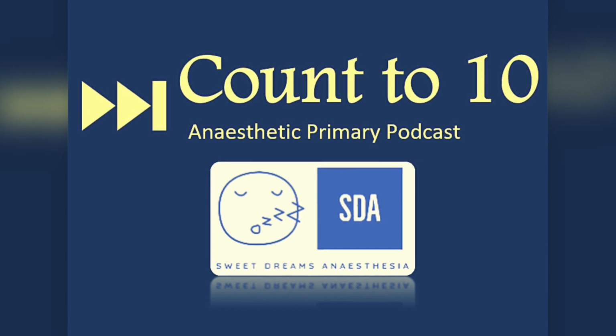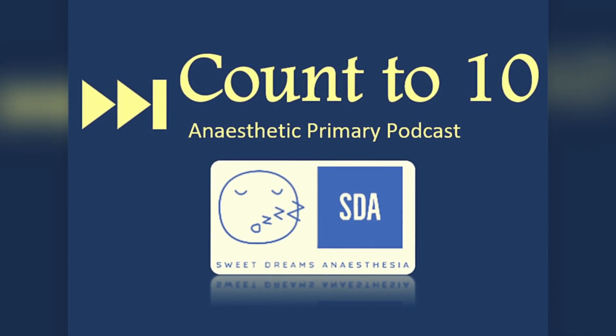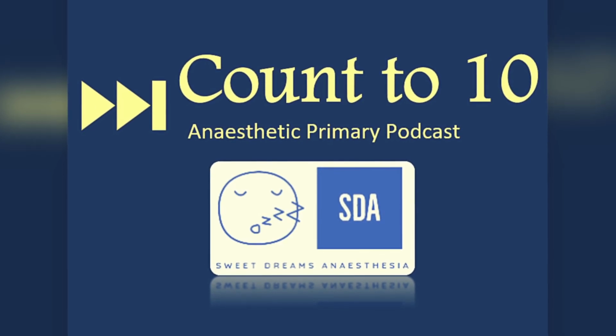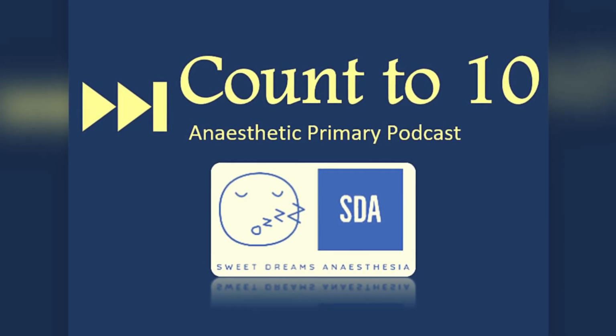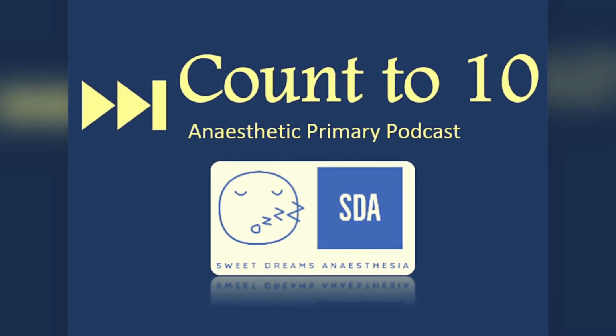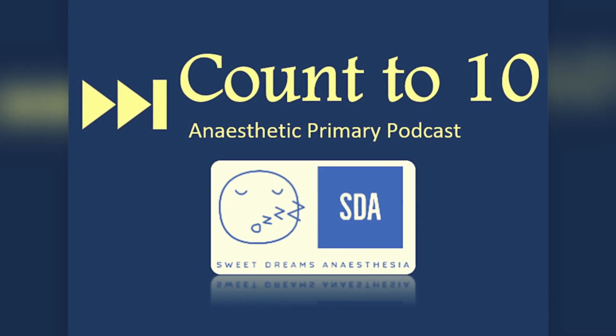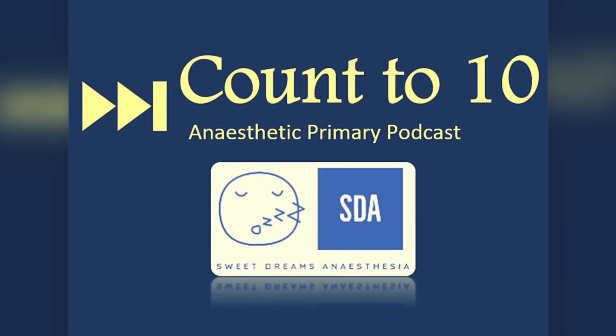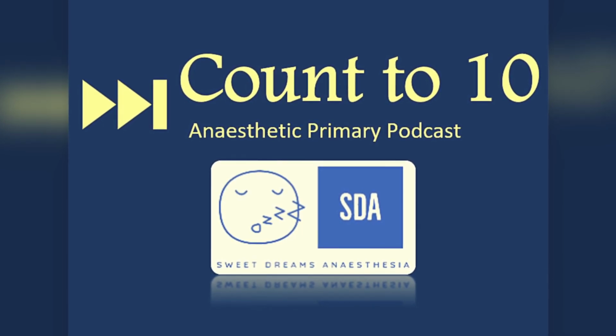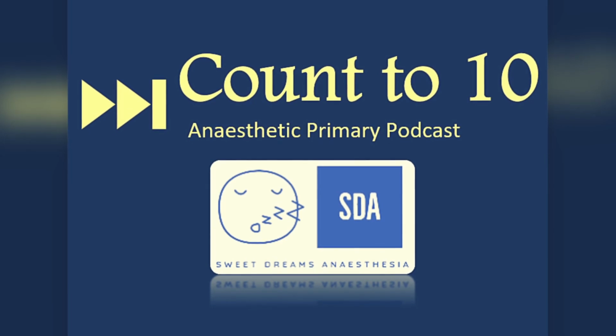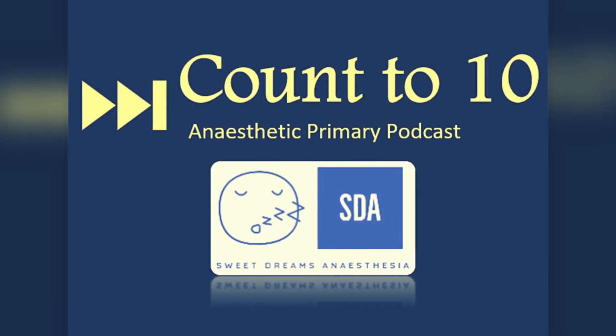A body plethysmograph essentially puts a patient into a box, and here we use Boyle's law to help calculate airway resistance. Remember, Boyle's law describes that pressure is inversely proportional to volume. So when we put a subject into a closed box, we know that the pressure and the volume are going to change with the patient breathing in and out. The pressure inside the box is atmospheric pressure. When the patient inspires, they change their lung volume, and this therefore changes both the pressure inside their lungs and the pressure in the box.